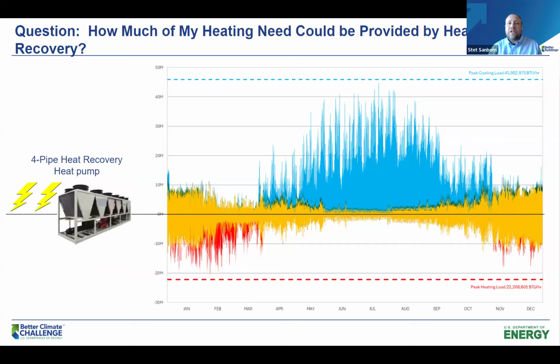An alternate solution is replacing that chiller with what we call a 4-pipe heat recovery heat pump. This is an air source piece of equipment, but it can do both heating and cooling and simultaneous heating and cooling. So now one piece of equipment is doing all the things at different times of the year, but you're not doubling the size of the infrastructure required to support that system. This is key. Work within your electrical budget instead of trying to just put in a new technology.